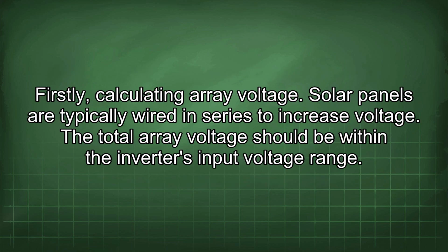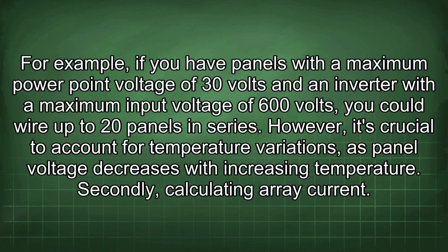Firstly, calculating array voltage. Solar panels are typically wired in series to increase voltage. The total array voltage should be within the inverter's input voltage range. For example, if you have panels with a maximum power point voltage of 30 volts and an inverter with a maximum input voltage of 600 volts, you could wire up to 20 panels in series. However, it's crucial to account for temperature variations, as panel voltage decreases with increasing temperature.